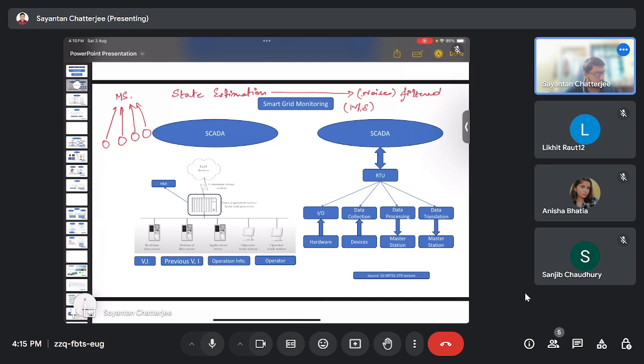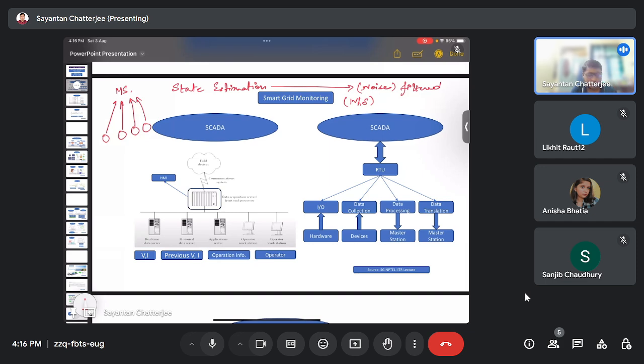In the present context, since we'd be discussing the SCADA system - SCADA is installed at the substation or master station on the HMI, and it's the software where data is fetched from RTUs deployed in the field. We can also use the term IEDs, intelligent electronic devices, which are deployed throughout the field. That data is delivered to the substation where the SCADA system is installed, and through the human machine interface, we get an idea of the operating states.